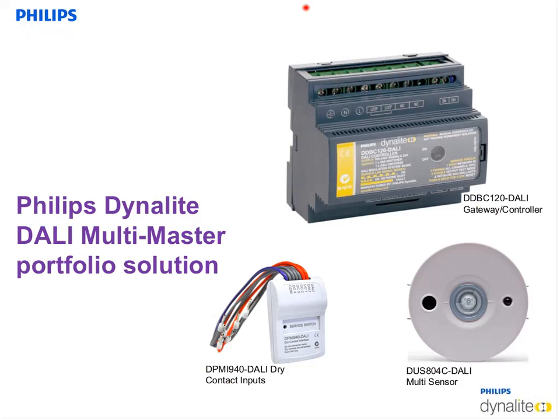What does the DALI Multimaster portfolio look like? Well, very small in fact. We have our intelligent device here. This is our controller. We can operate a universe of 64 drivers connected to here. So one DALI line. In addition, we can connect a number of sensors, which I'll come back to in a moment. And we also have what we see for the first time, a dry contact.